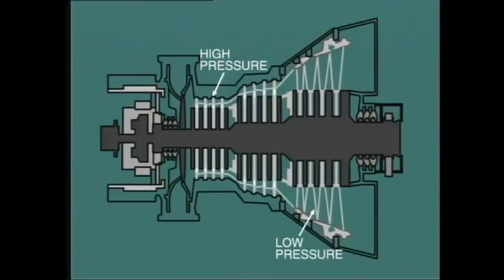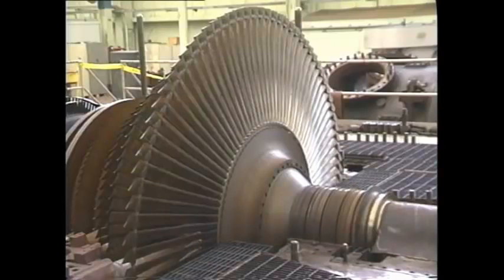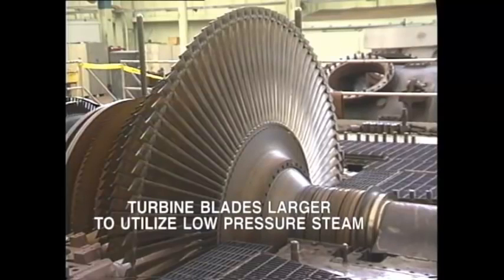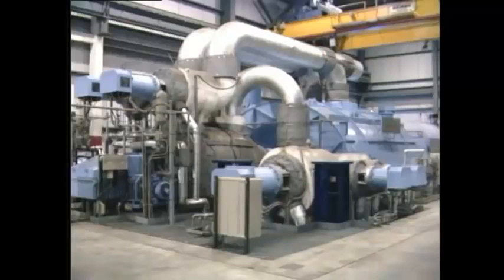So one clear consequence of this is that we have to make the casing continuously bigger as we move from the high pressure to the low pressure end. This is very evident to the eye when we look at this single-cylinder turbine. But notice, it is not only the casing that must be made bigger, but the turbine blades must also be larger in order to utilize this low-pressure steam. On turbines of high output, say above 100 megawatts, it becomes physically difficult to make the cylinder large enough to accommodate all of the low-pressure steam.